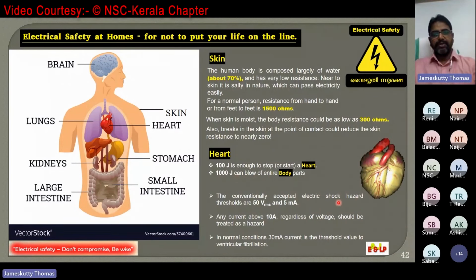Then we will study step potential and touch potential later, and these are the 50 volt. I will explain later that it is the threshold voltage that can create damage to our body. Then about 10 ampere, regardless of voltage. Another question I want to ask you is which is dangerous, voltage or current, which is creating accidents. We shall explain that later. So 10 ampere current, regardless of voltage, voltage is not a matter, should be treated as a hazard. In normal conditions, 30 milliampere current is the threshold value to create ventricular fibrillation. I explained ventricular fibrillation.